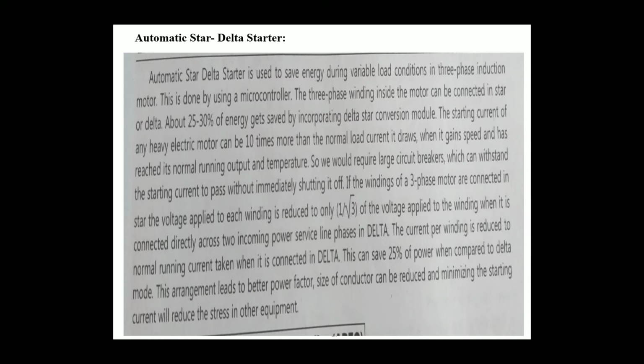The next is the automatic star delta starter. The automatic star delta starter is used to save energy during variable load conditions in a three-phase induction motor. This is done by using a microcontroller. The three-phase winding inside the motor can be connected in star or delta. About 25 to 30% of energy gets saved by incorporating a delta star conversion module. The starting current of any heavy electric motor can be 10 times more than the normal load current it draws when it gains speed and has reached its normal running output and temperature. So, we would require large circuit breakers which can withstand the starting current to pass without immediately shutting it off.